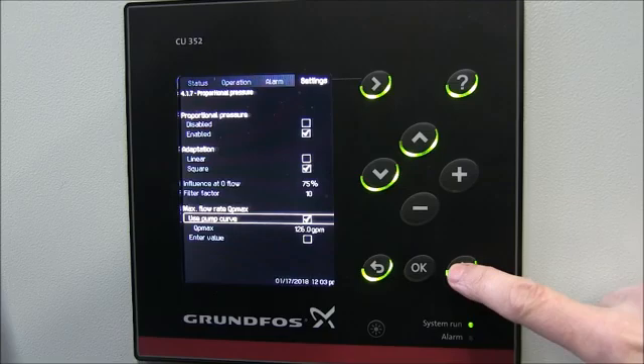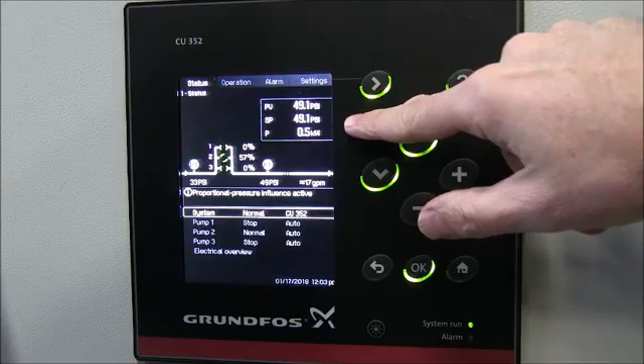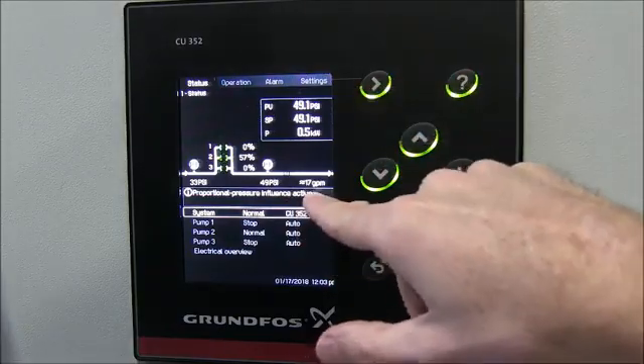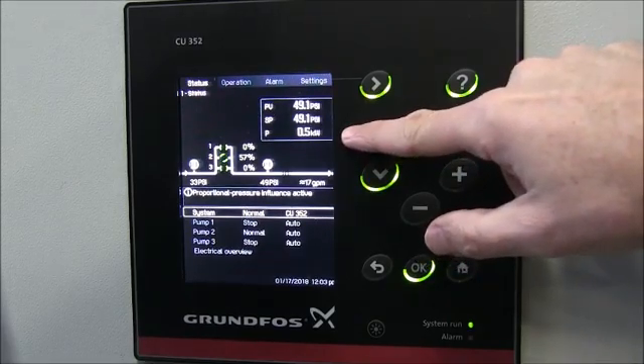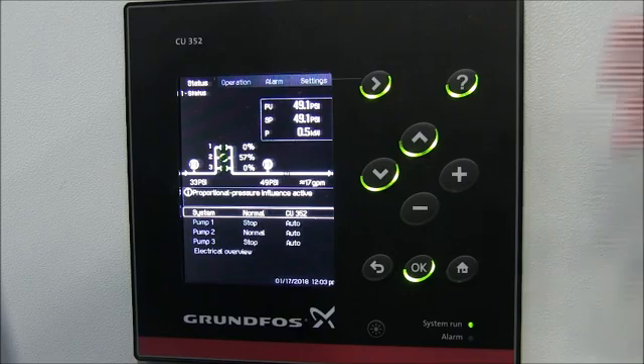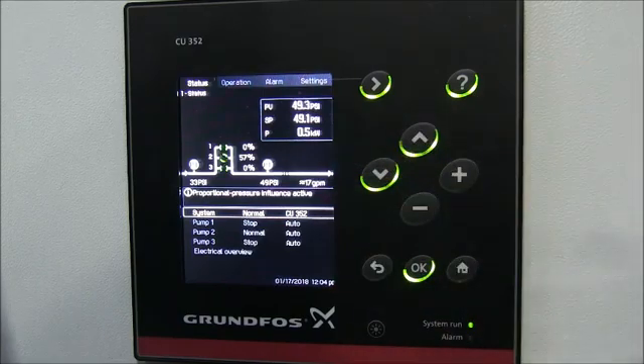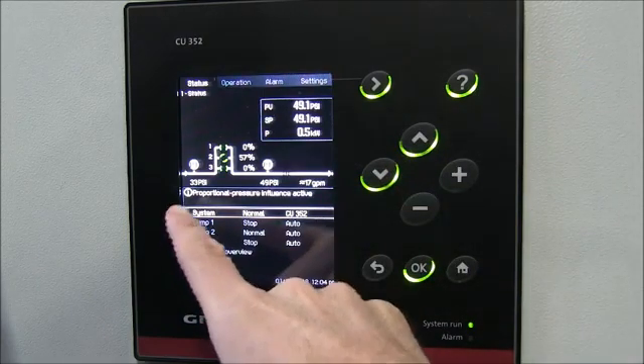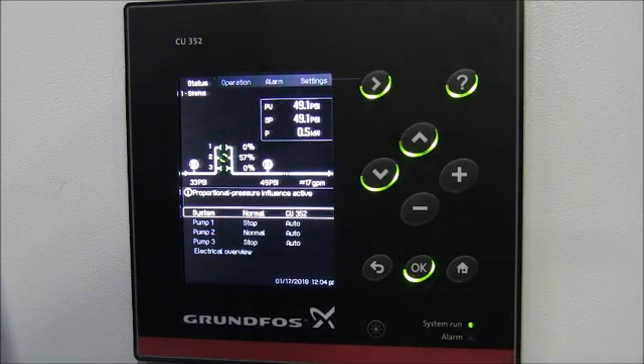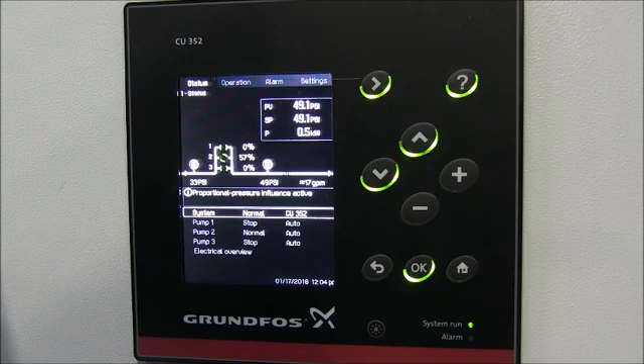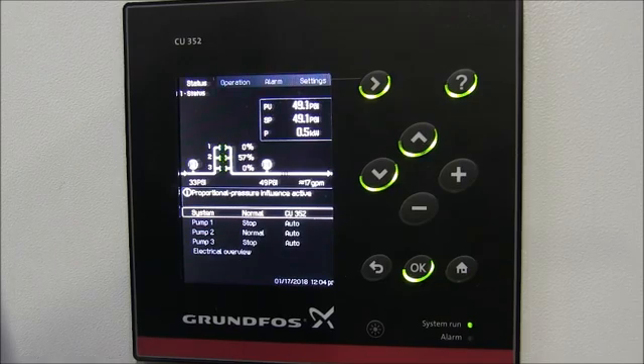Hitting our Home button takes us back to the main status screen. We can now see that our new set point is 49 psi. Our flow rate is a little bit lower — closer to zero — and notably we've reduced our power down to 0.5 kW. So with proportional pressure, we went from about one kilowatt at low flow down to half a kilowatt — you can see the energy savings impact. There's also a message that says 'Proportional Pressure Influence Active,' letting operators know that proportional pressure has been deployed and explaining why the set point is 49 psi instead of 65 psi.